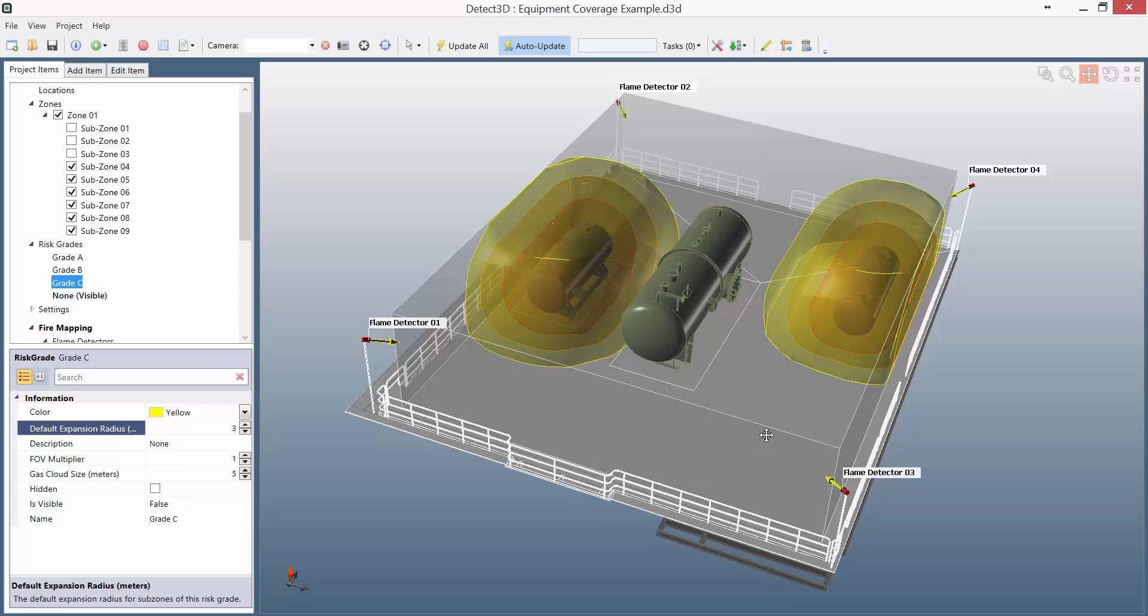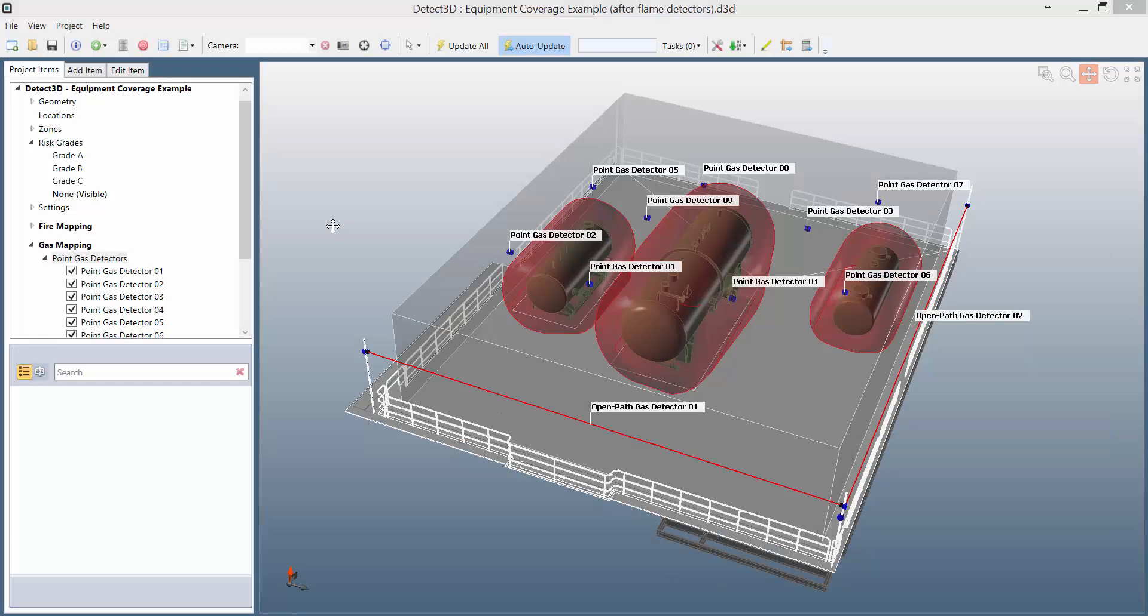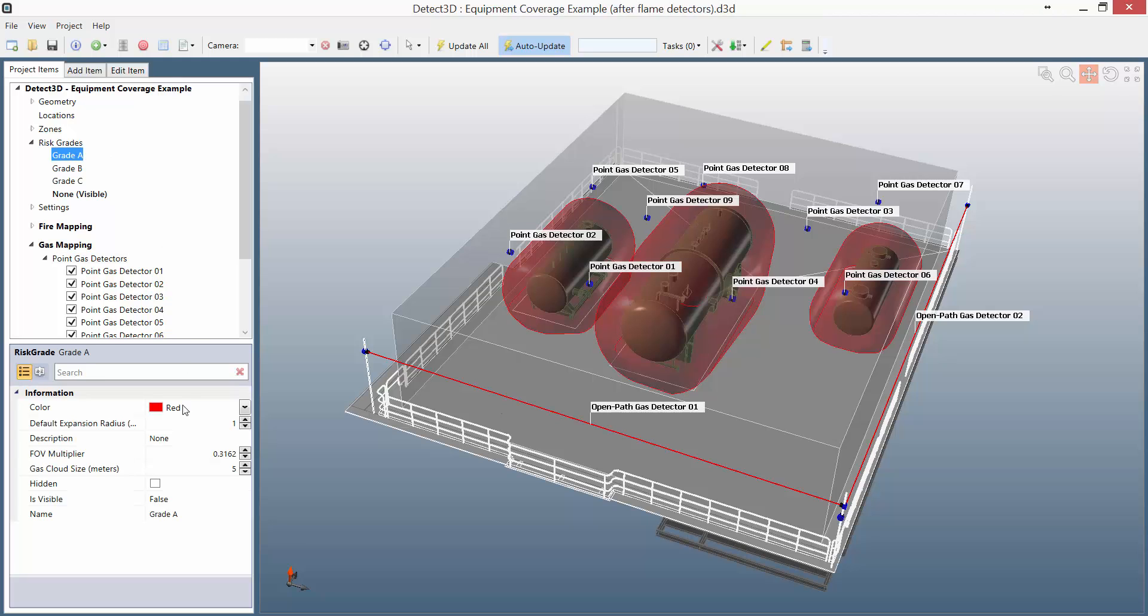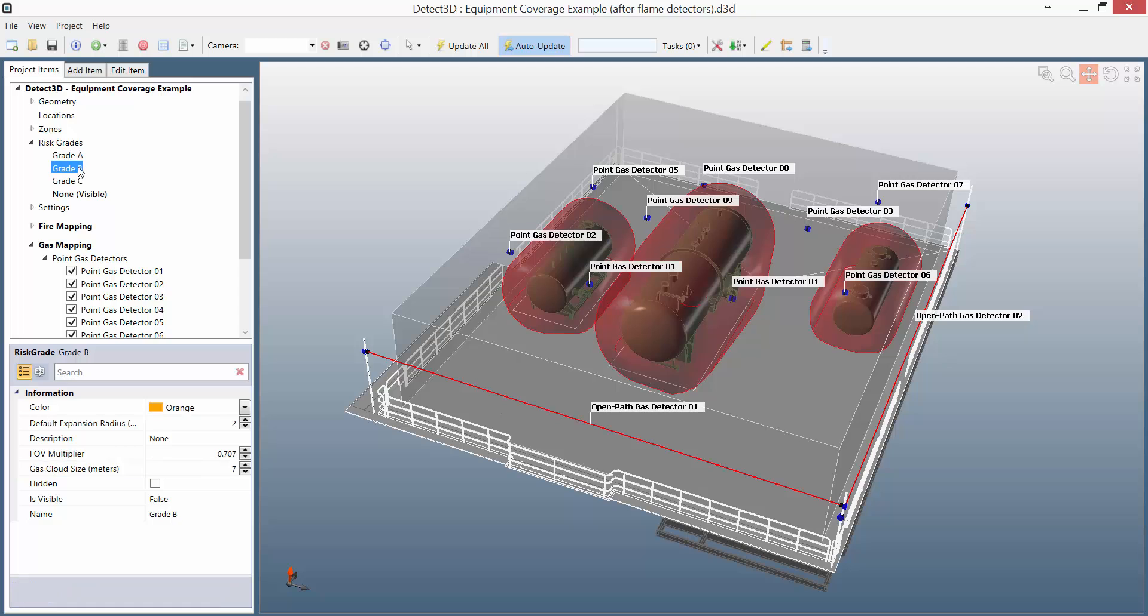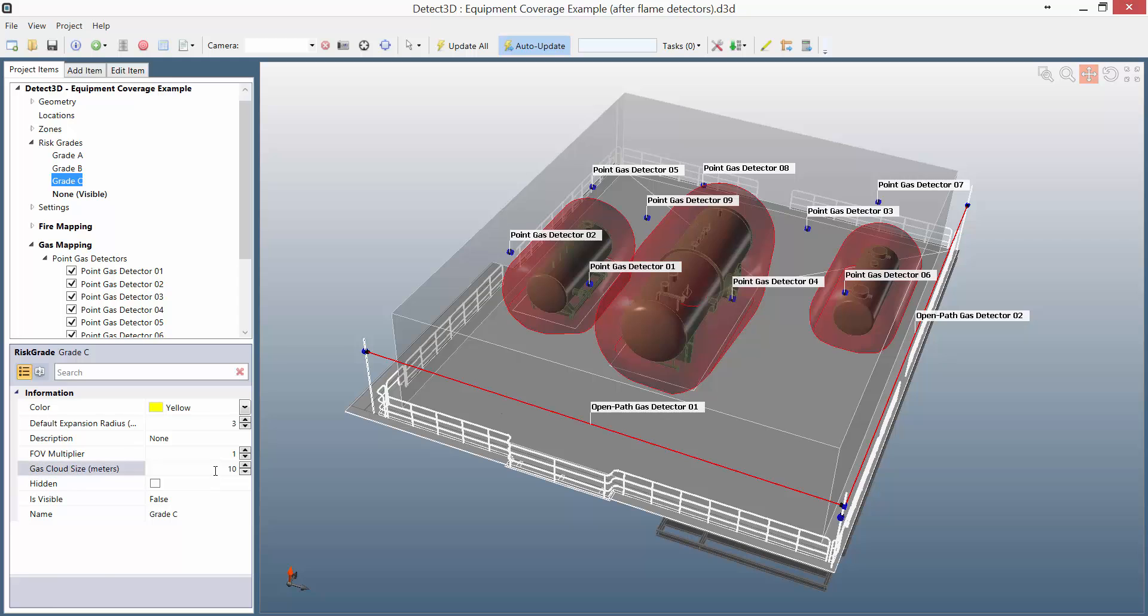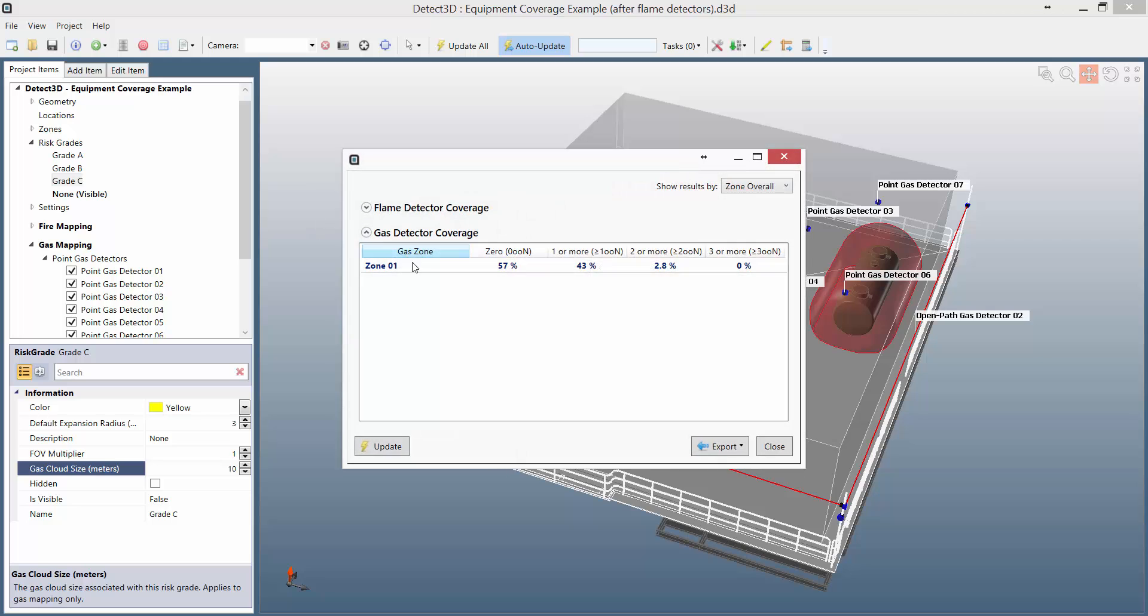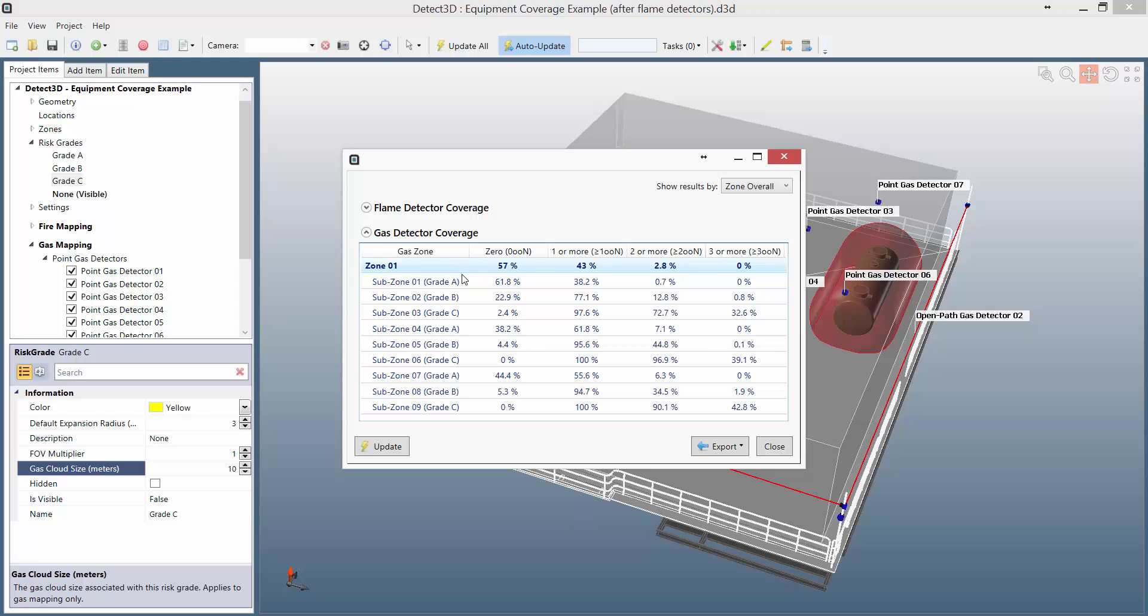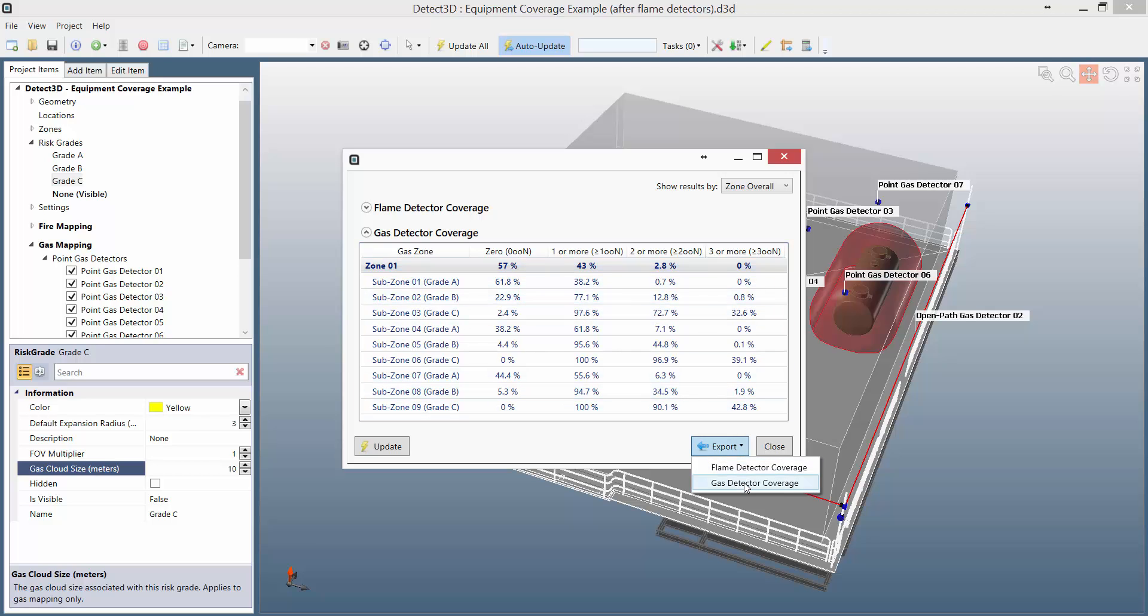Now this capability isn't just for fire detectors. I'm going to show you the exact same thing for gas detectors. Here I've got point and open path gas detectors defined, and instead of field of view multipliers, I've got different gas cloud diameters for each risk grade. And similar to the fire mapping, for the gas mapping, the coverage for each risk grade is evaluated on the local cloud diameter for that risk grade. I can also see the coverage for each individual subzone around the equipment, and I can export all this data to an Excel spreadsheet.